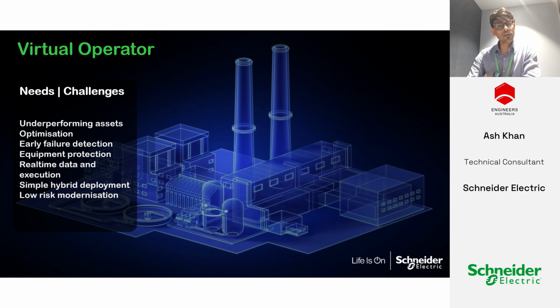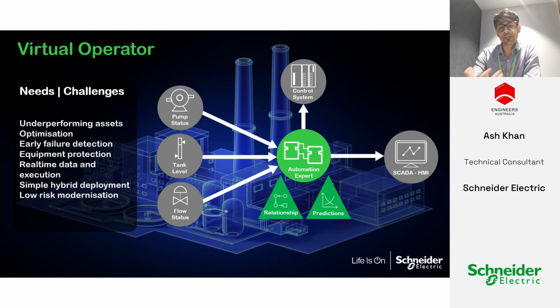Virtual operator, this is an interesting one. This is for deploying on a brownfield site, where it can be used just for monitoring an existing process. It looks at pump statuses, tank levels, and flow statuses, brings it into Automation Expert, and does relationship checks of different assets like valves and pumps, to make sure the statuses and levels of those assets are correct. For example, if a valve is open and the pump is running, or a valve is closed and the pump is running, and another valve is closed, it can do a complex relationship evaluation and give insight into whether the process network is in the correct state.